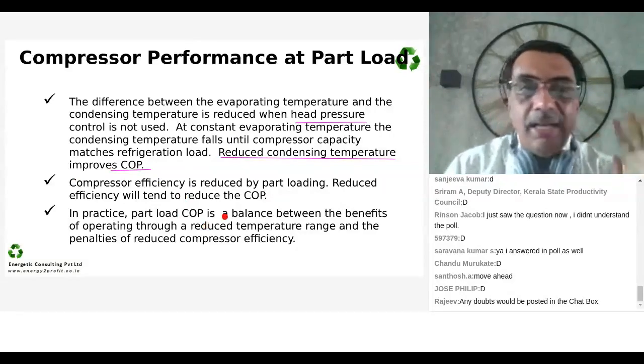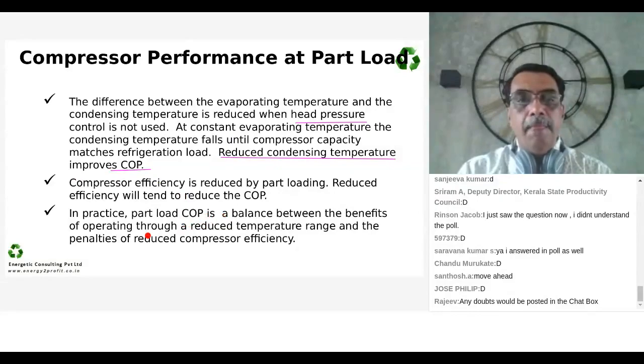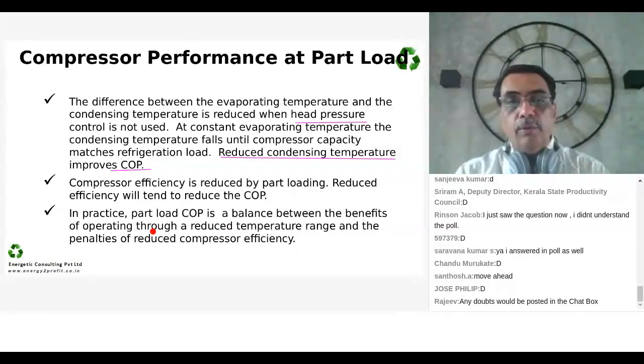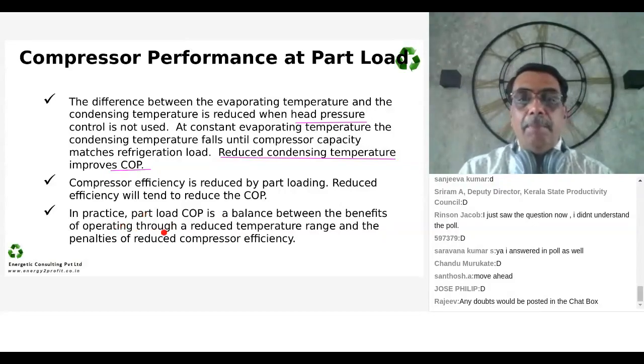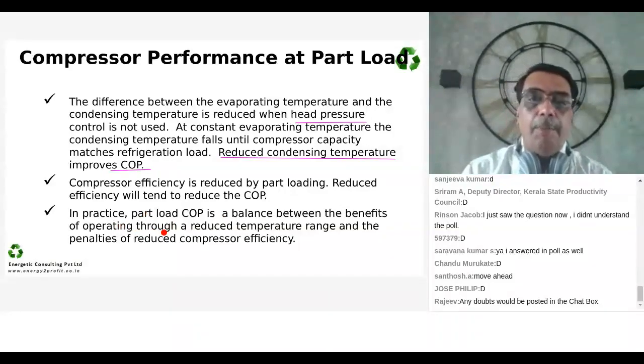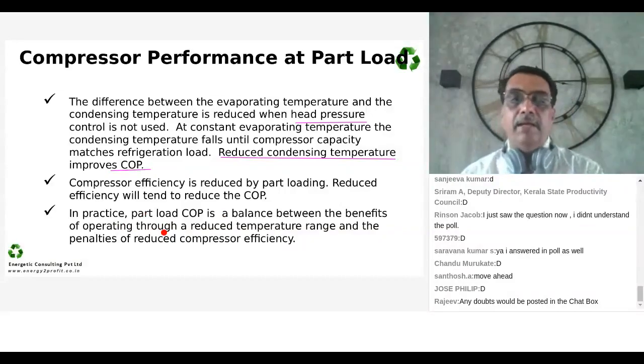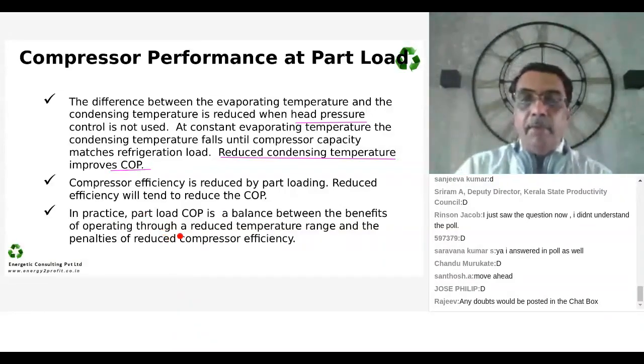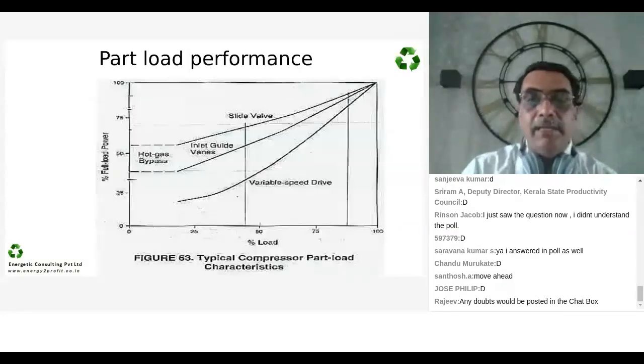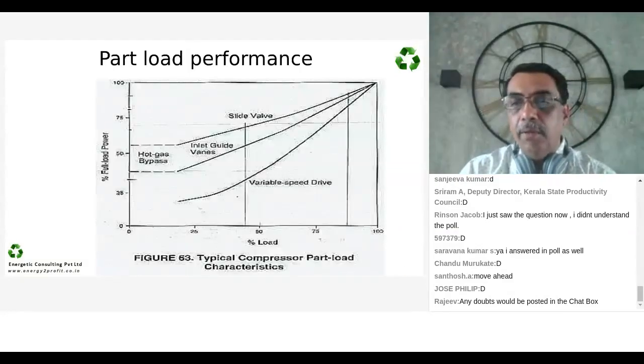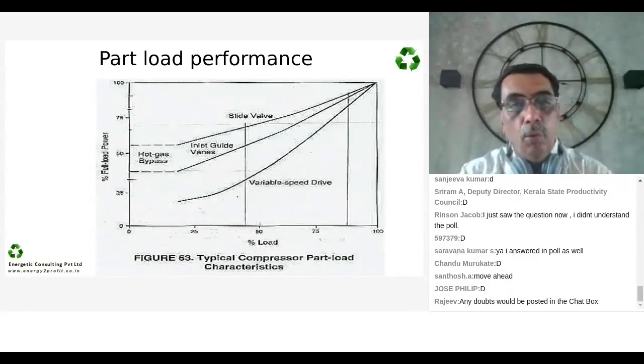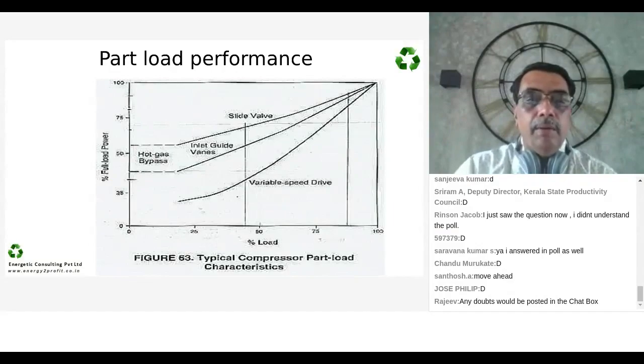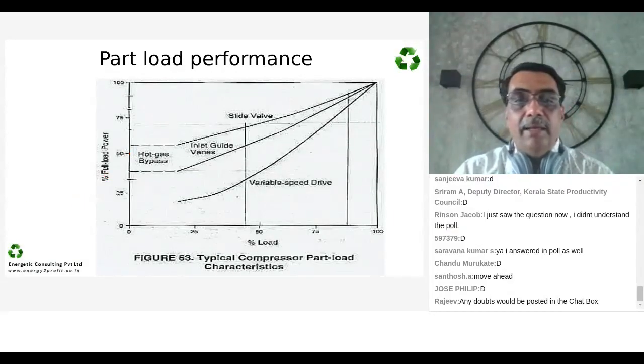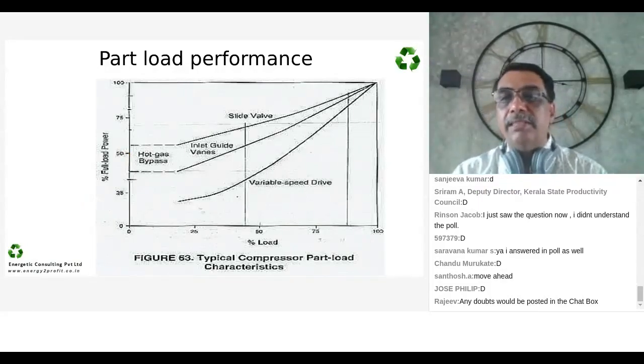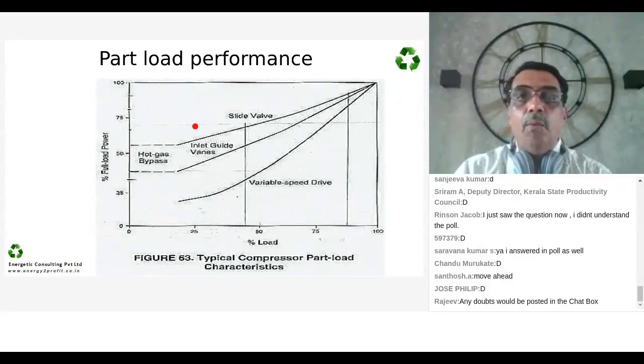Part load compressor efficiency is definitely compromised, which means that the COP tends to reduce. What it means is that the part load COP is the benefit of operating at a reduced temperature range and the penalty of reduced compressor efficiency. So running a compressor at part load is a compromise. It does not work at full capacity, full load. Now, we are moving to the next part in the discussion. And why I'm spending so much time and going a little slow on this is because this is fundamental. What are the arrangements available?